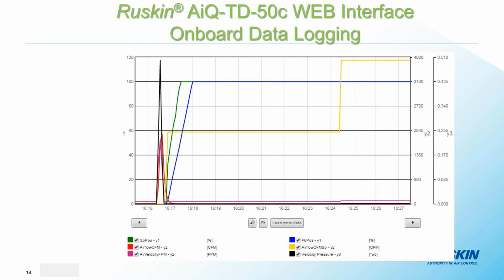The actuator, by the way, has built-in data logging. It will log for 30 days or 6 months, depending on whether you pick compressed or non-compressed data logging. But this data logging lives inside of the actuator, and so you just come up to the actuator, plug in your laptop, and you're able to download this information directly from the actuator as an Excel spreadsheet, and then take it back to your office for analysis.